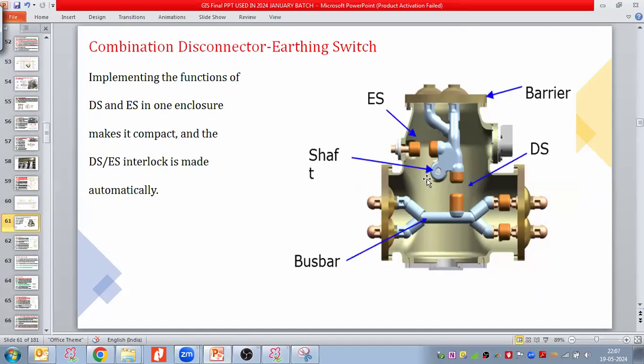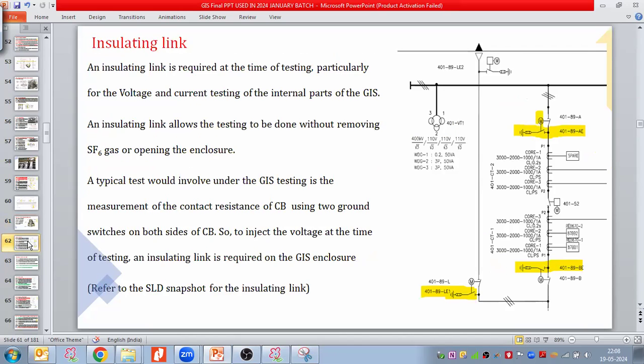So disconnector here, this is shaft for the movement purpose. Here, earthing switch. Here we have the bus bar. With the help of the shaft and drive mechanism, we move this arrangement inside the module. So implementing the function of disconnectors and earthing switch in one enclosure makes it compact, and the disconnectors earthing switch interlock is made automatically. So this is the advantage taking both combined type disconnectors and earthing switch module.